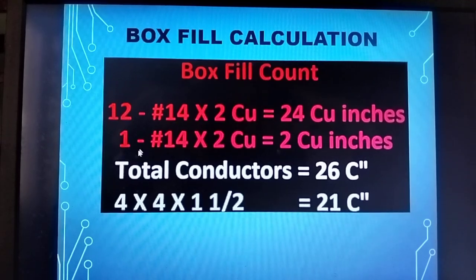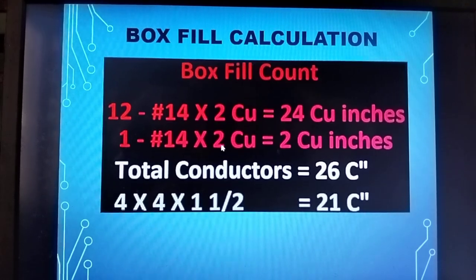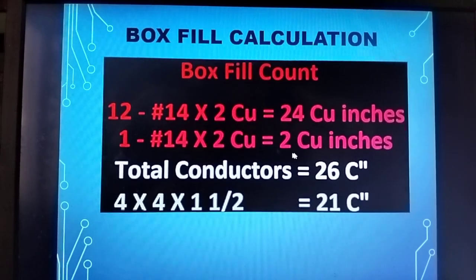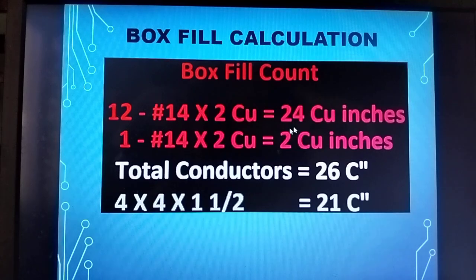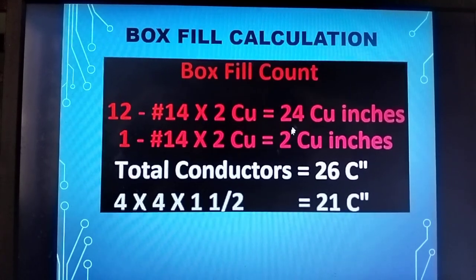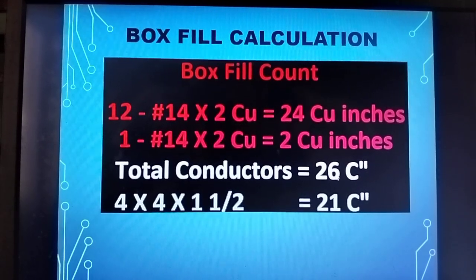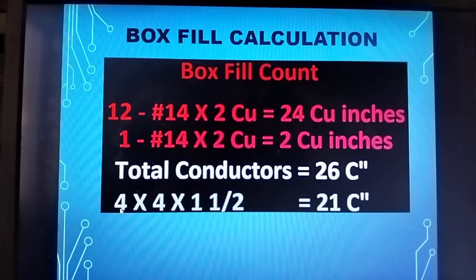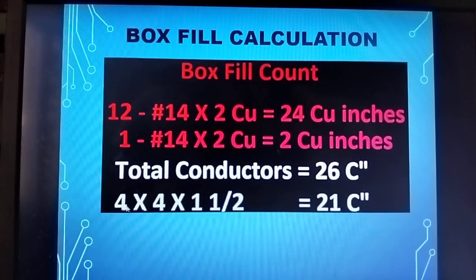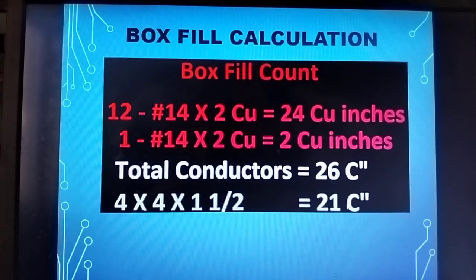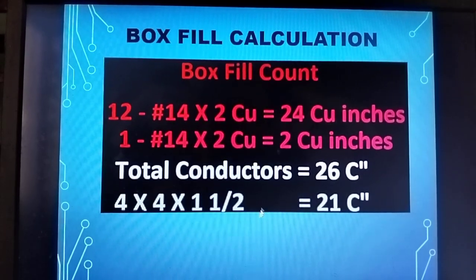Then you have cubic inches for the ground conductor, so 2 cubic inches you add, so it will be 26 cubic inches. If you use 4 by 4 by 1.5, it's only 21 cubic inches. So this is undersized. You must not use this because the total is 26.